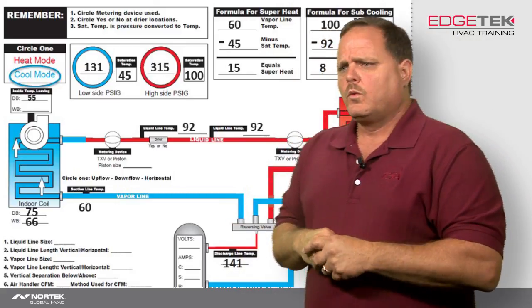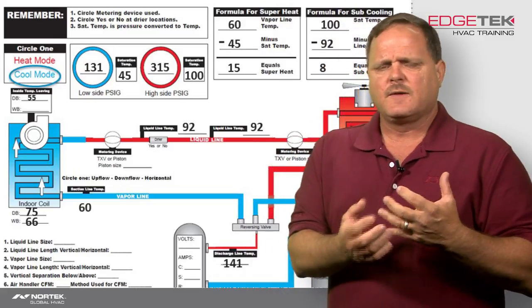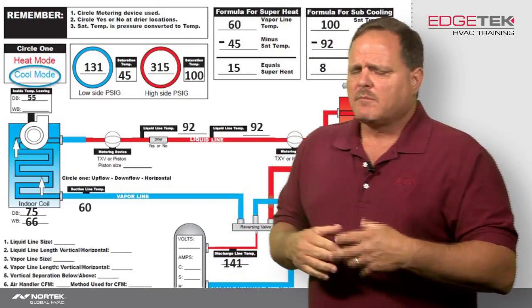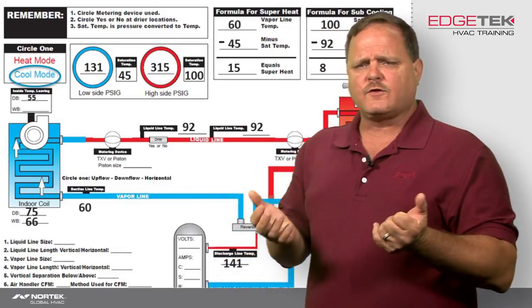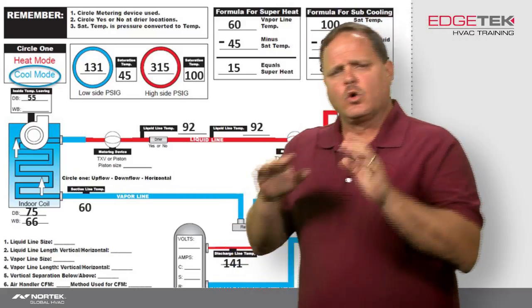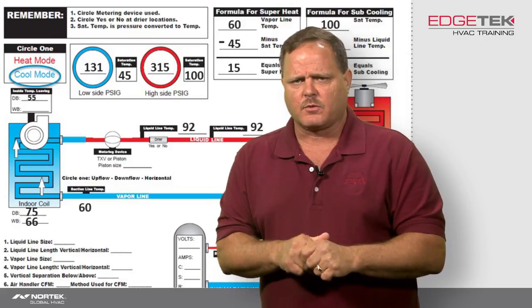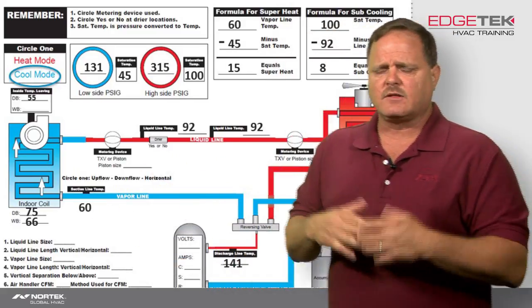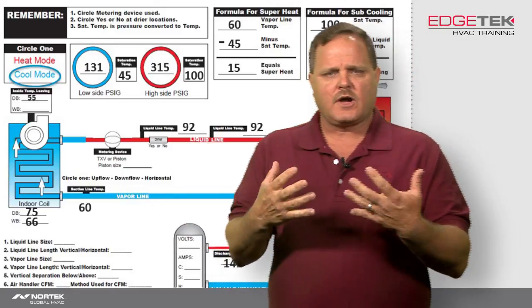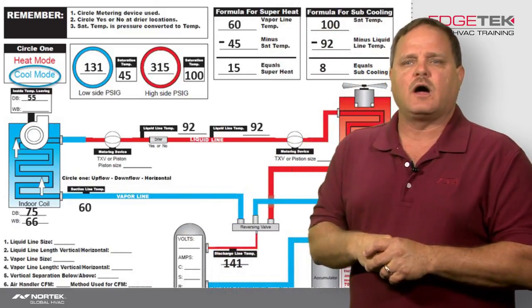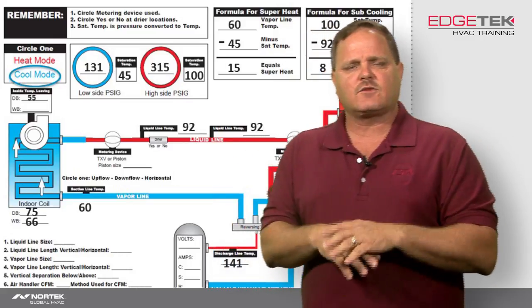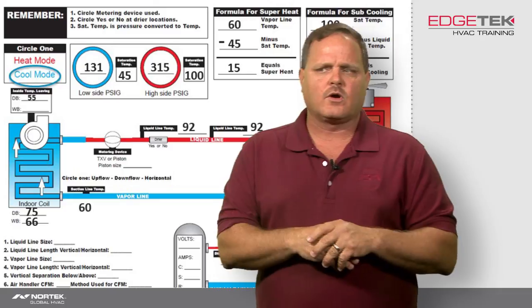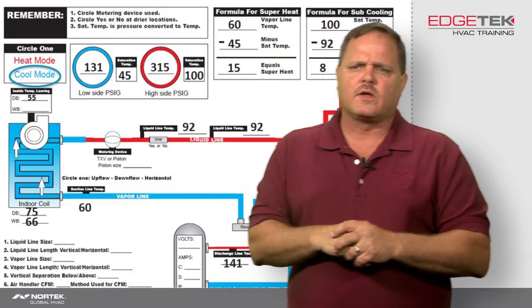When troubleshooting a system with a piston, we don't look at subcooling as much as superheat, because load conditions are going to change what that superheat is — that's why you've got to use the slide calculator. The hotter it gets outside, the more pressure you're going to have behind that orifice, pushing more refrigerant into the evaporator. Cooler outside, the head pressure goes down and less refrigerant gets pushed into the evaporator. The indoor wet bulb is absolutely critical: higher wet bulb means higher latent load and higher humidity, which creates more load on the evaporator and drives your superheat up as well. The load conditions play a big role in what that required superheat is going to be, so there's no set superheat with a piston system.